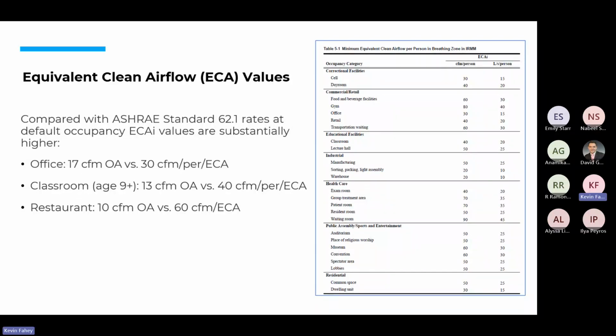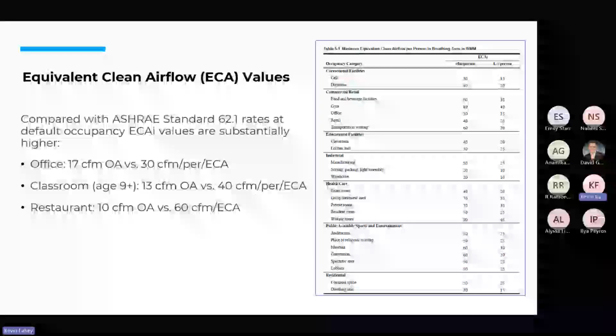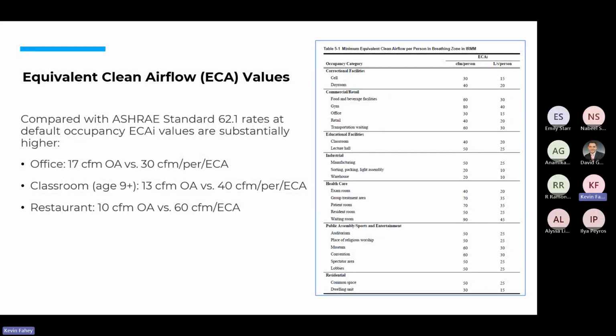So equivalent clean air is required if the authority requires this infection risk mitigation mode. What does that do in an office environment right now? If you're using the ventilation rate procedure, you're requiring approximately 17 CFMs of outdoor air. With the equivalent clean air requirement, if in the infection risk mitigation mode, you're going to require 30 CFMs of equivalent clean air. In a classroom, it's going to jump from 13 CFMs to 40, 3 times the amount. And in a restaurant type of environment, it would jump from 10 CFMs to 60, 6 times the amount.